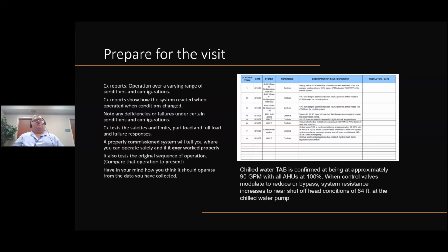That's key if you're going to try the same thing on one of your ECMs, since you may change the configuration or approach to something different that they might have tried at commissioning, and they came up with a result that may be good or bad. I've done that before, where we improved the performance of the system with a minor change, but I also found out you don't want to do this, and I would note that. That's where these comments come in.